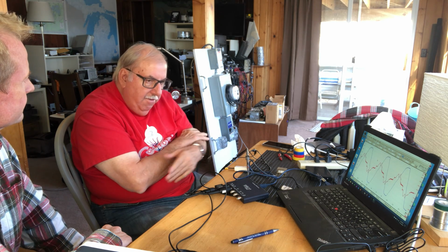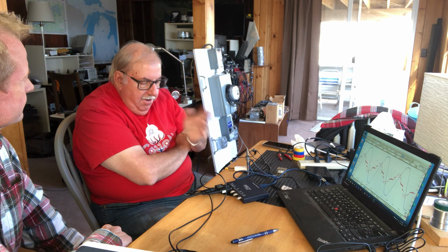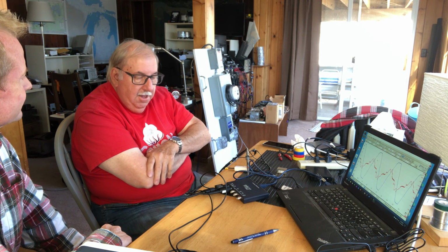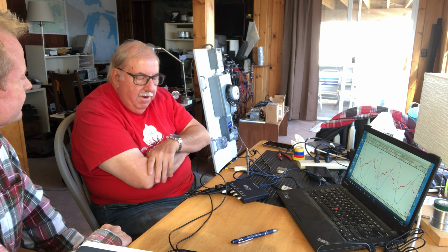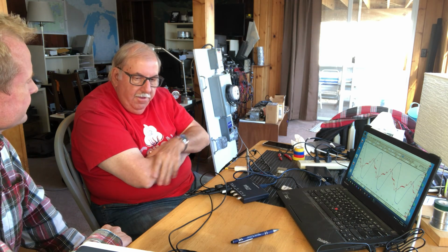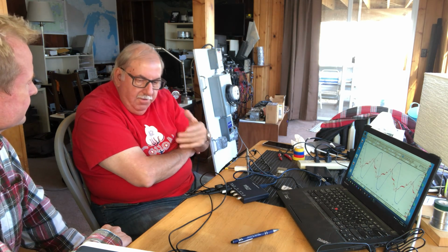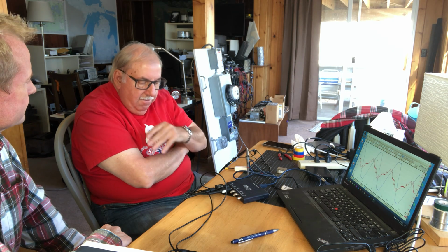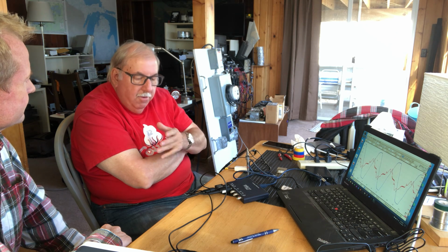After we got this all fitted out, all the equipment changed out, they're getting ready to do their first launch with all the IBM ATs installed. And as we were getting close to the launch time, the noise created by the power supplies in the IBM ATs was creating a disturbance on all the sensors on the space shuttle, on the rocket boosters and the liquid fuel tank and the telemetry on the pad and all. Everything started getting unstable readings.